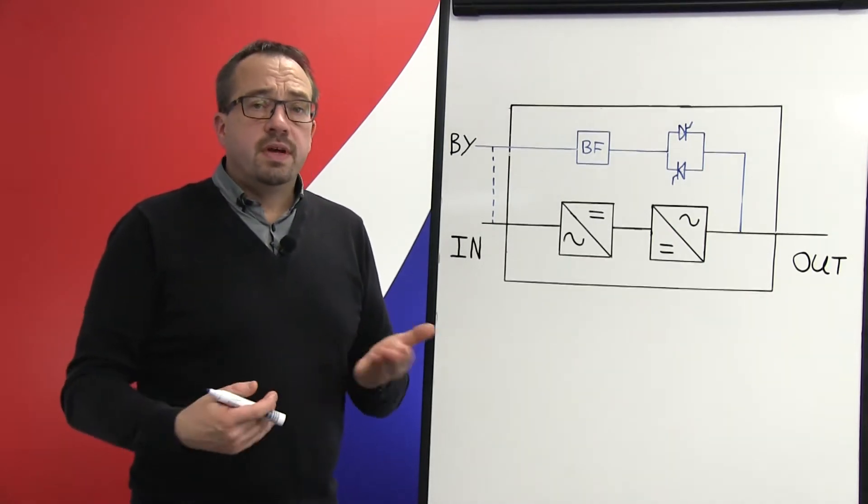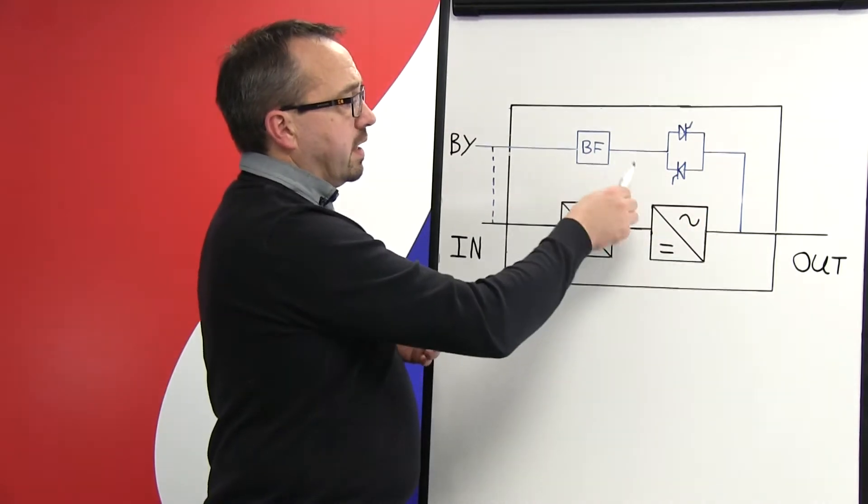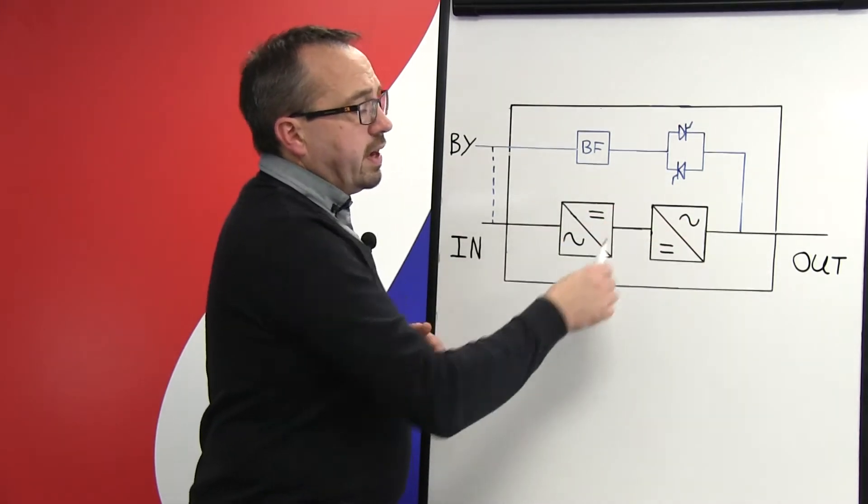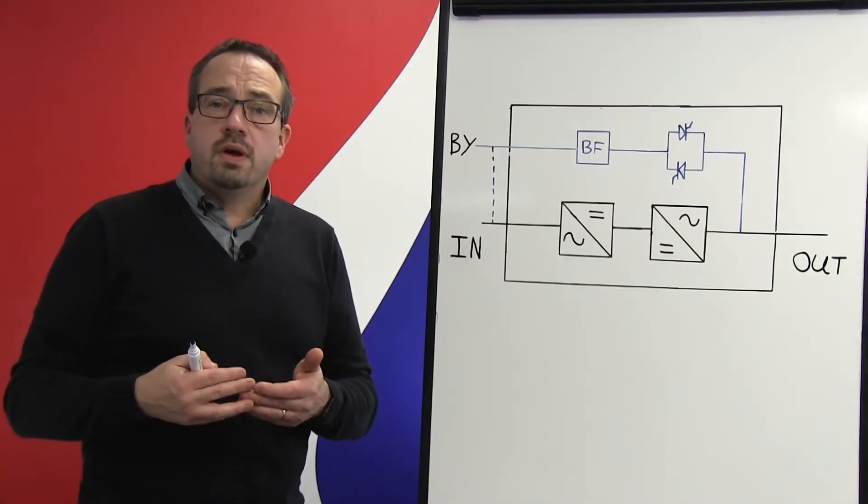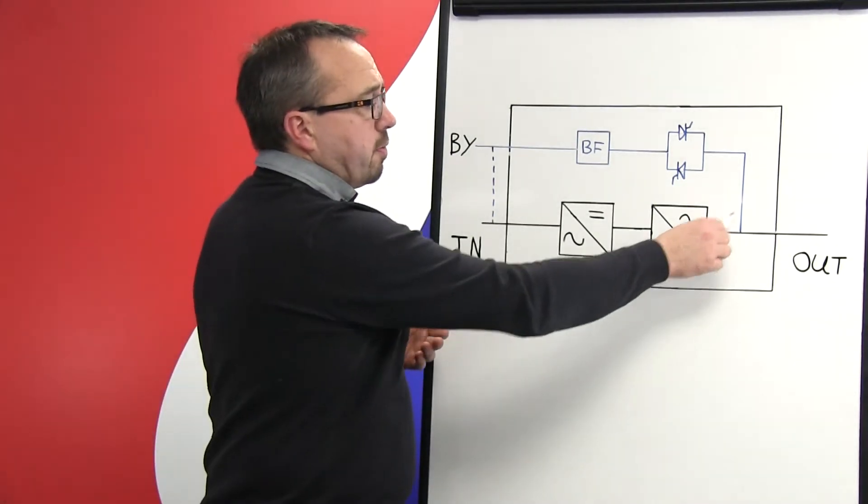Now the reasons that can cause the UPS system to automatically transfer the load from the inverter onto the bypass line include if the inverter or the rectifier were to fail, or there was a problem with the controlling architecture within the UPS system which meant that the output voltage waveform from the UPS was having a problem or was beginning to collapse.